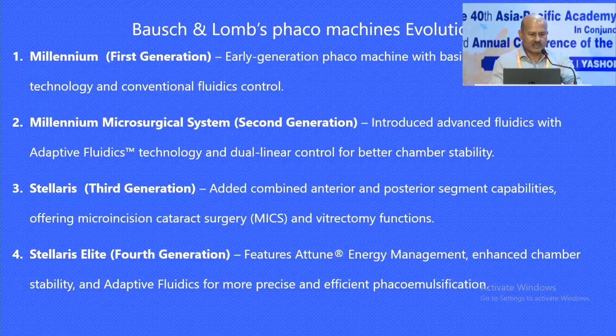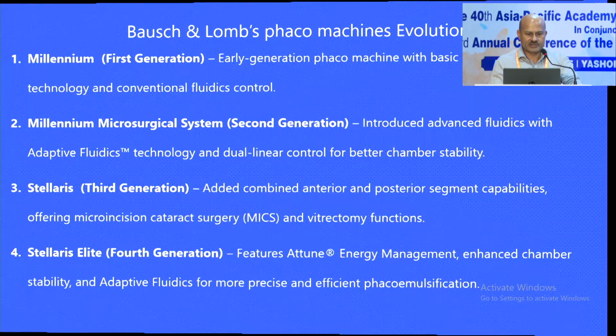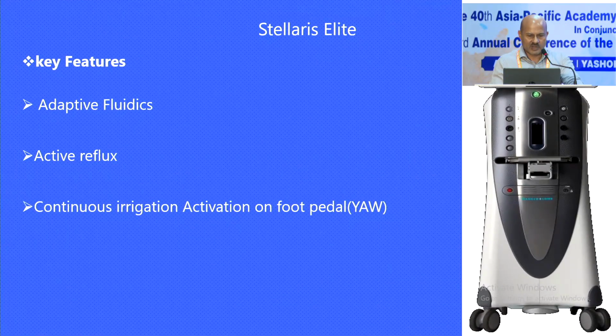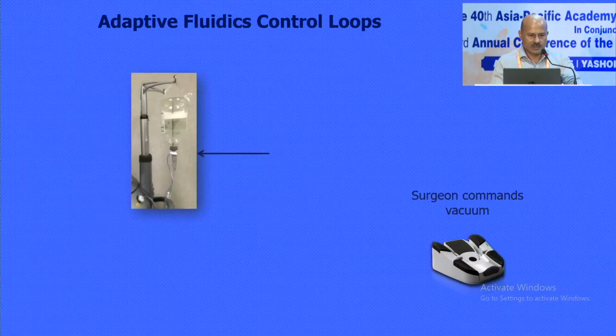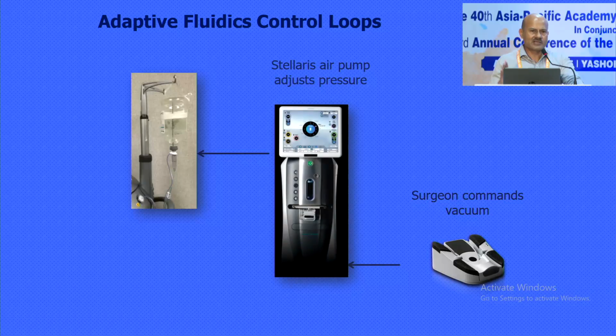According to Bausch and Lomb, the Stellaris, then the Stellaris Elite, fourth generation. Again, they have developed on two sides, the power delivery. So here the adaptive fluidics has an active reflux which controls the reflux and the surge, and a yaw movement on the foot pedal: up, down, and the yaw movement. What they have done is, for the bottle, they have a pressure infusion. Instead of the plates used by the Alcon machine, they have a pressure infusion into the infusion bottle. So depending on the surgeon's foot pedal movement and the vacuum feedback, the infusion is maintained by an active pressure method. So that is what happens in the Stellaris machine, the fourth generation.